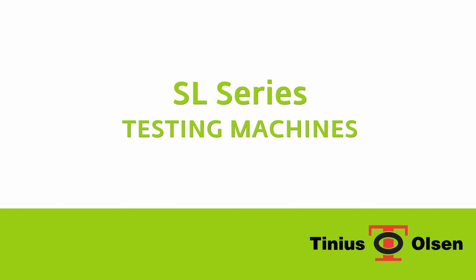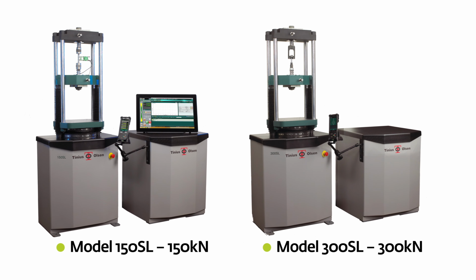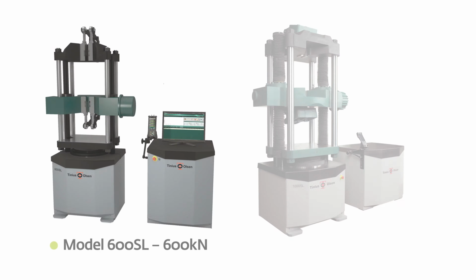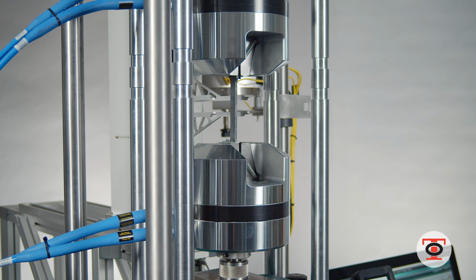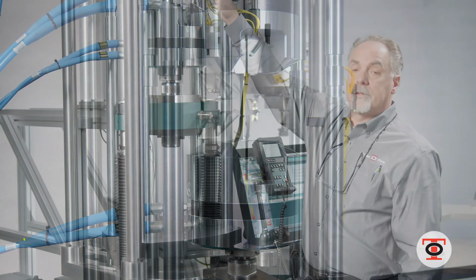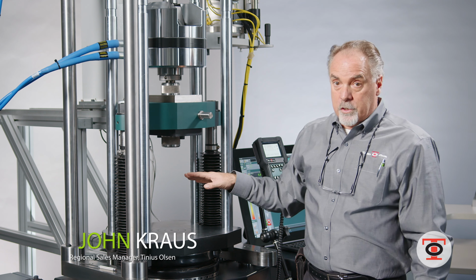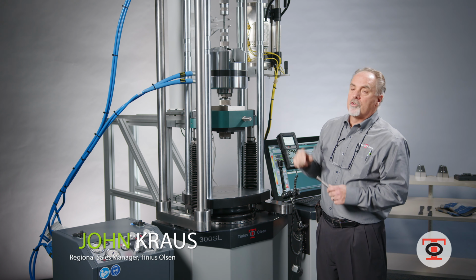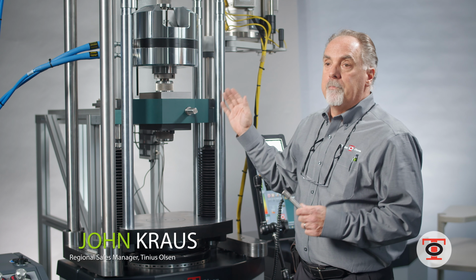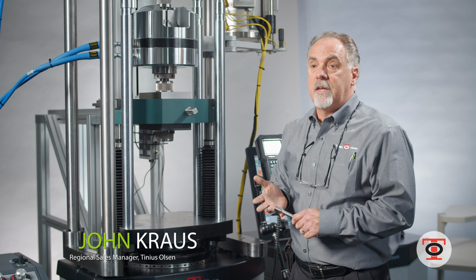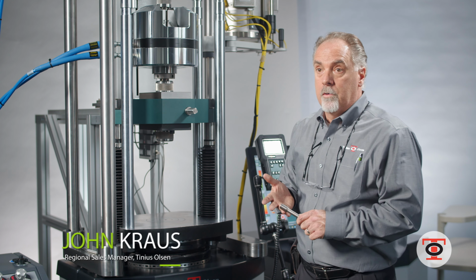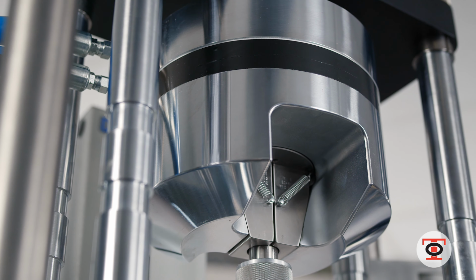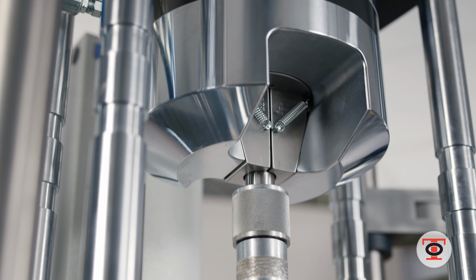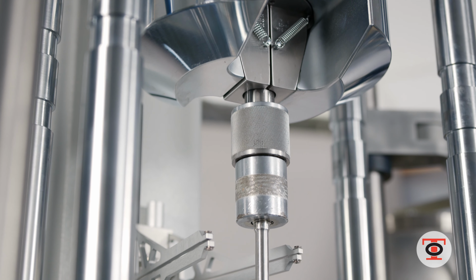The 300 SL is a 4-column design. The 150, the 600, all the way up to the 3,000 kilonewton machines are all 4-column design. The SL line can be configured for different tests: tensile, compression, flexure, peel, so it's truly a universal machine. It meets or exceeds the ASTM standards, the ISO, or British standards. These machines are all over the world and meet the standards for each specific country.